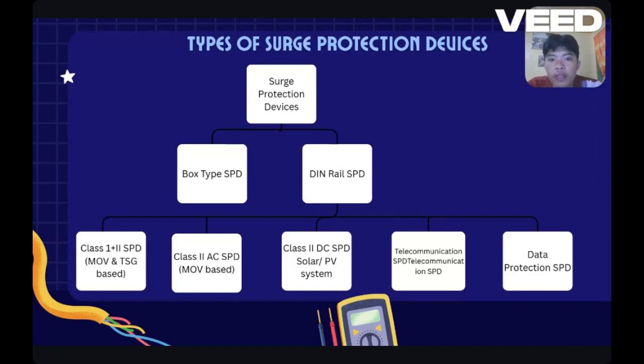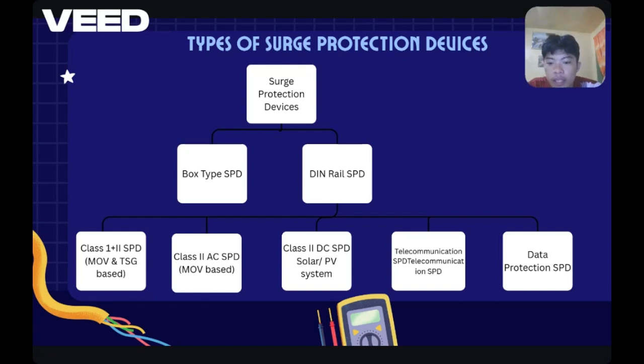We have types of surge protection devices. First, surge protection devices is SPD. Then you have two types. We have box type SPD and then DIN rail SPD. In DIN rail SPD, they have class 1 plus 2 SPD, MOV and TSG base. Then class 2 AC SPD, we have MOV base. Class 2 DC SPD for solar PV system. Telecommunication SPD. Then data protection SPD.